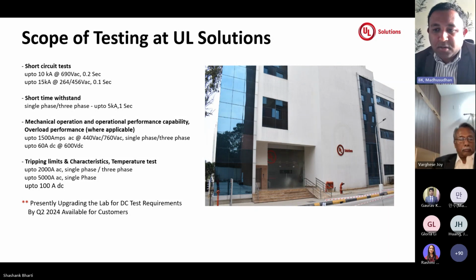And adding on to that, to conduct the mechanical and electrical endurance setup. For electrical endurance, we have up to 1500 amps AC, which covers 440 and 760 volts range for single phase and three phase. And also at the moment, we have a small facility for DC up to 60 ampere at 600 volt DC. And adding to that, for temperature and tripping characteristics, we have a 2000 amps AC source for single phase and three phase, and also a 5000 amp single phase source for supporting temperature rise and tripping characteristics. And also a small portion of DC we have with up to 100 ampere DC presently.